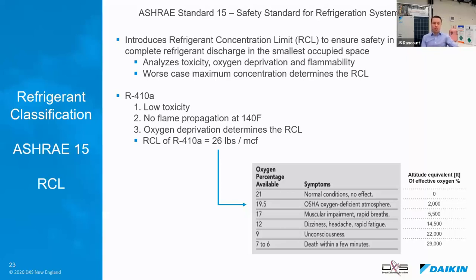So this is why engineers need to abide by this 26-pound limit, or stay close to it, to make sure that there's no issues. Now, this standard assumes that the space is sealed. Obviously, by code, all of our buildings have certain ventilation, but for safety purposes, it assumes that spaces are sealed and that you are stuck in that space. We'll come back to this later.